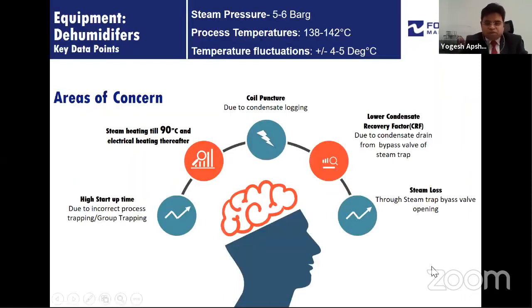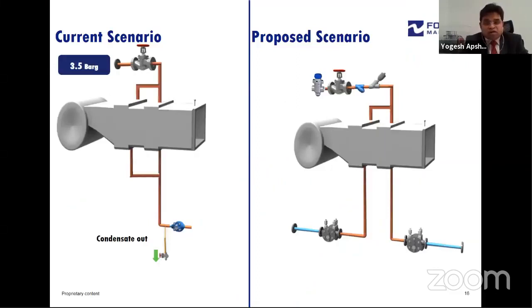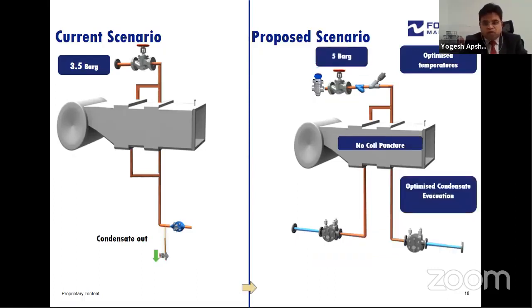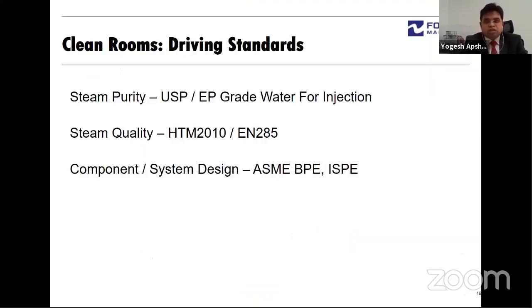Then coming to the dehumidifiers. For the dehumidifiers, we have seen similar data: the startup times are higher, with steam heating till 90 degrees Celsius and electrical heating thereafter. Then we have seen repeated coil punctures and repeated problems of low condensate recovery and opening of the bypass valves. So how have we addressed this? The steam is taken from a 3.5 bar tapping to a dehumidifier, and we propose to have a higher pressure of almost 5 bar gauge for this application. Then optimize the temperature control system and use individual trapping instead of group trapping. So this is the proposed scenario which makes the complete dehumidifier truly intelligent in its sense.